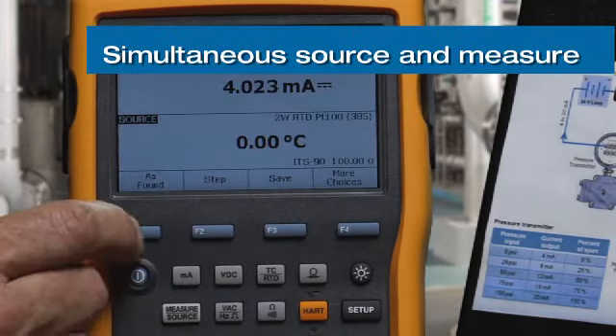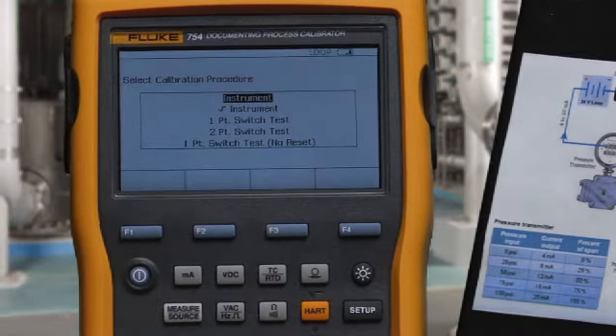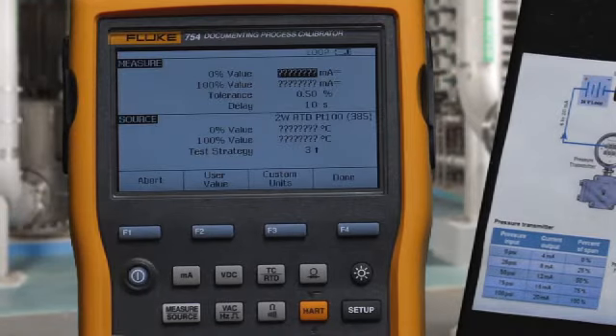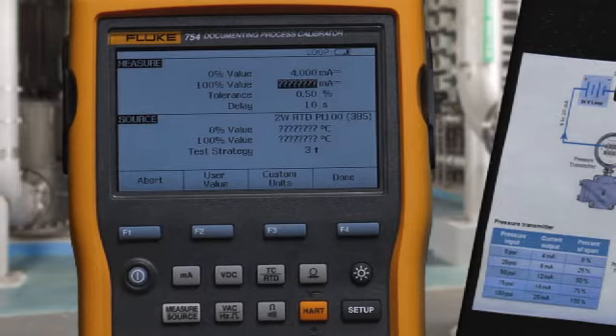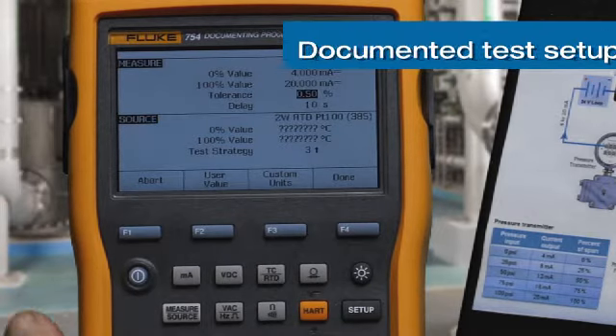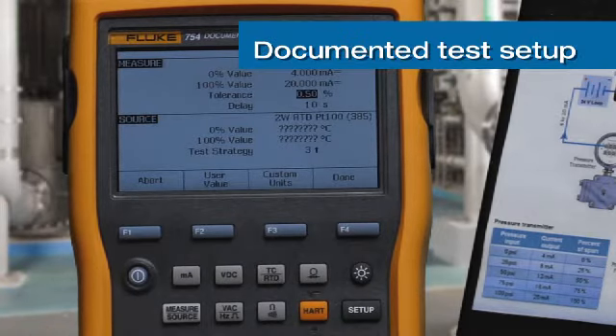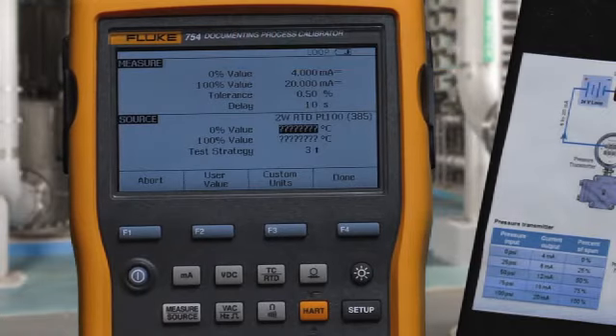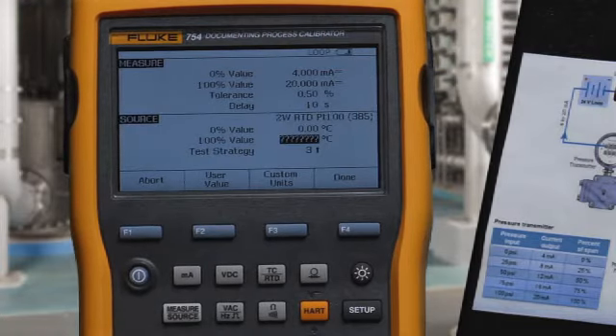We document the calibration as found for an instrument. We're going to measure 4 to 20 milliamps to a test tolerance of 0.5% while sourcing 0 to 300 degrees C.